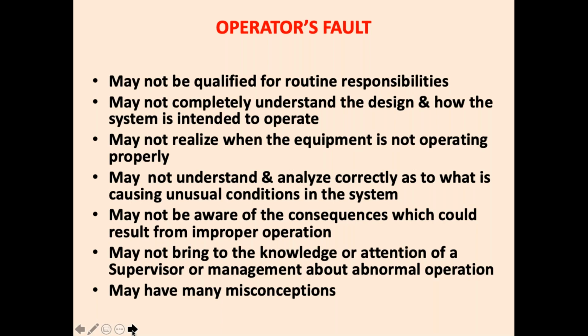A lot of operators I have seen, when the motor overloads, they close the liquid line. They say, "No, no, if I reduce the liquid supply, the motor does not overload." But that leads to low suction of the compressor, high discharge temperature, and your compressor can break. So there are many issues. Operators just do it without understanding what could be the consequences of not operating the plant properly.